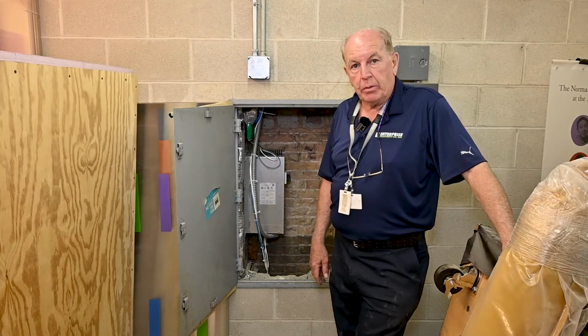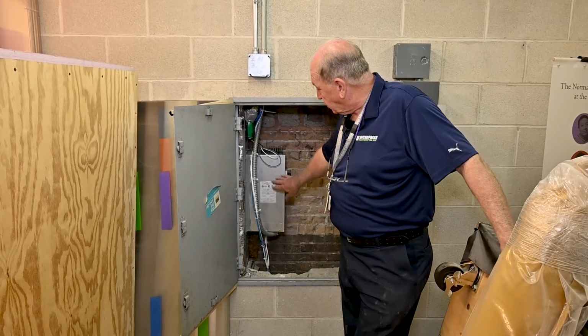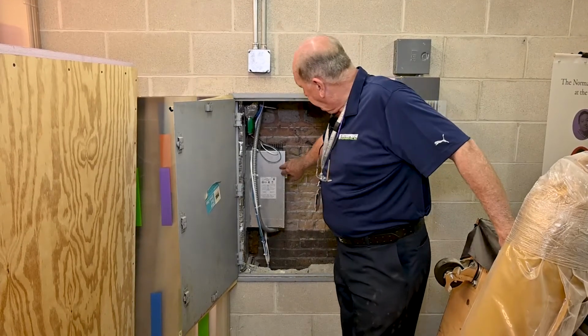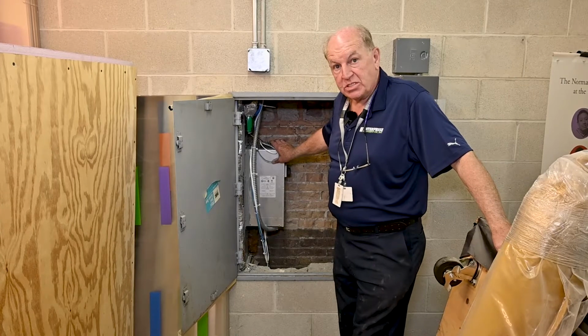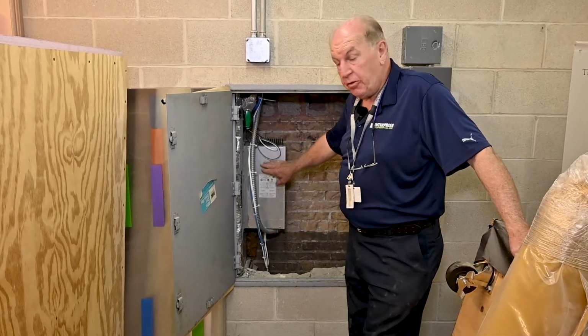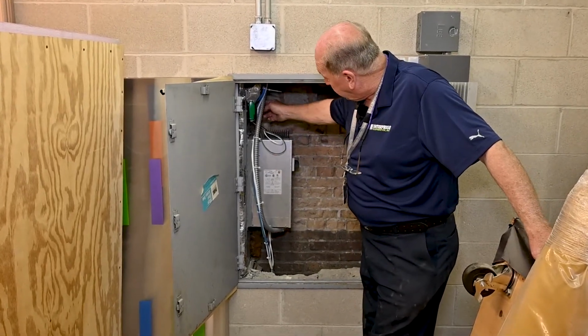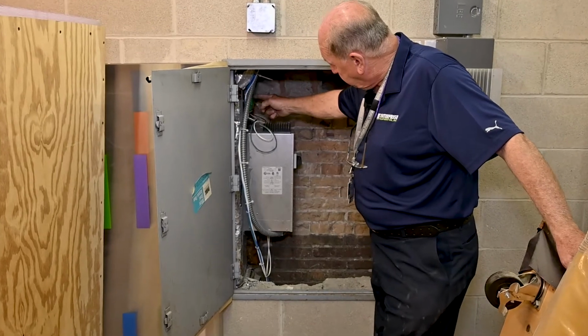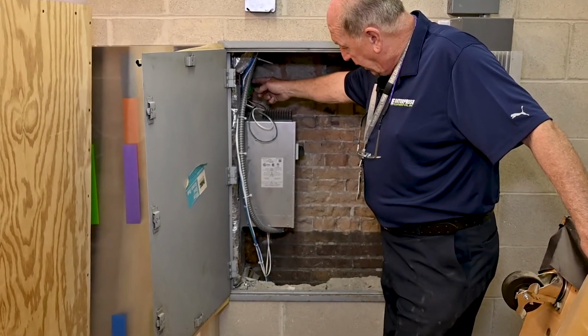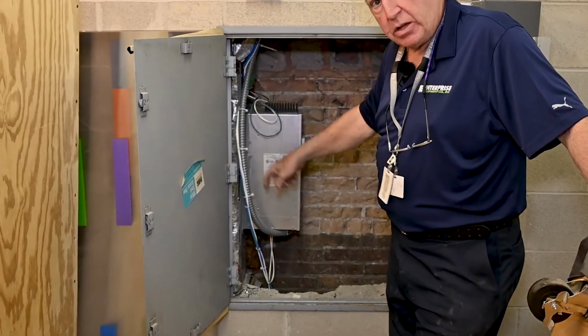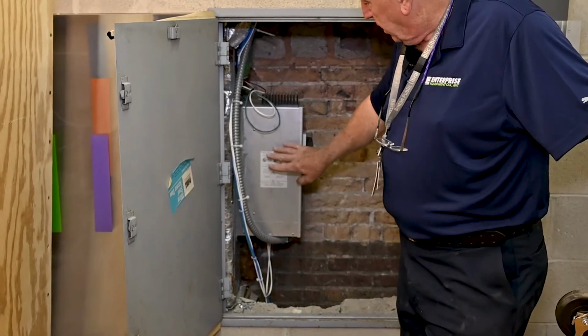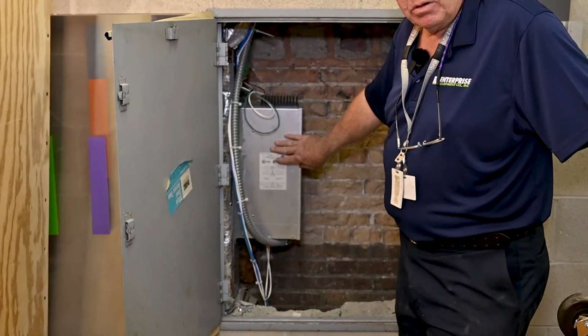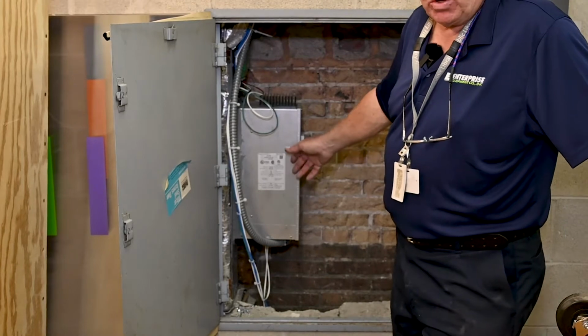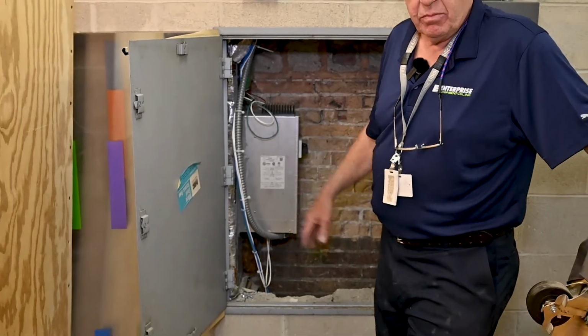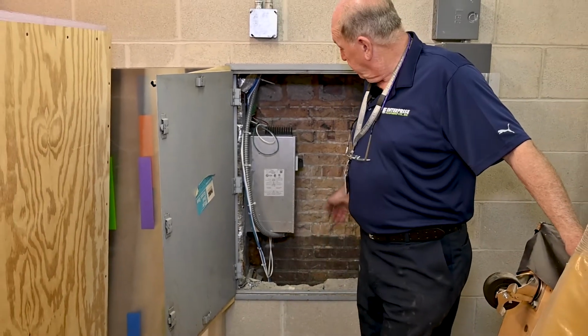That's it. We're at Copley Library Rare Books project, and this is an electric duct heater. It's 1 kW, 460 volts. Has a built-in airflow switch and the controller right here from the building management system. So when the air is flowing to that room, this will be powered and provides electric heat. It's just one spot where they didn't have steam heat for it.